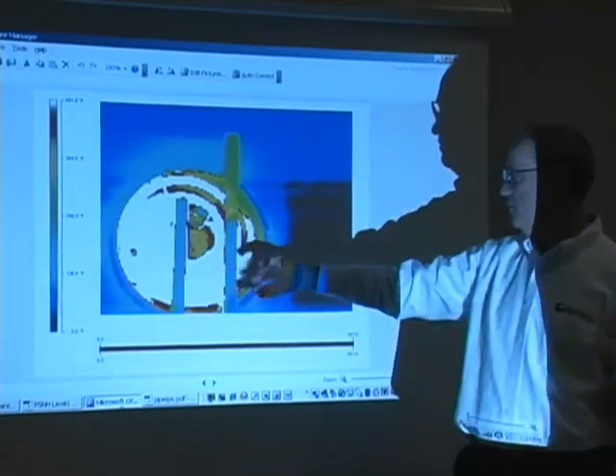This said 125 degrees. It has taken the reflection from outer space off the bright, shiny object, bringing it back to the camera, taking the actual temperature of the copper tubing, bringing it back to the camera, and it's doing some math.